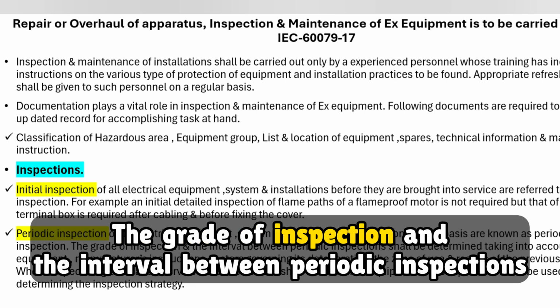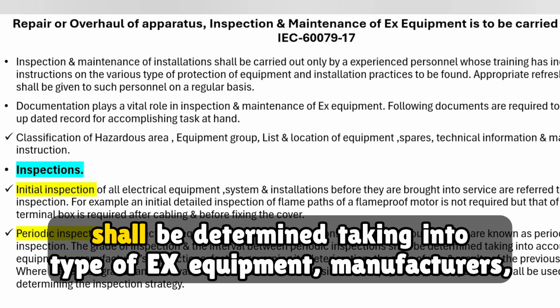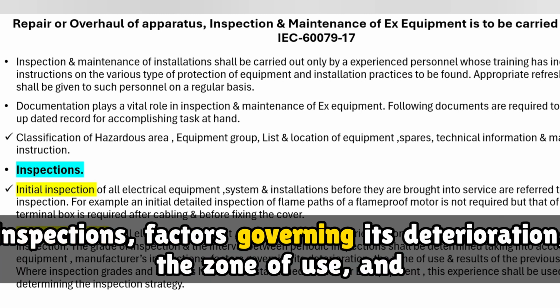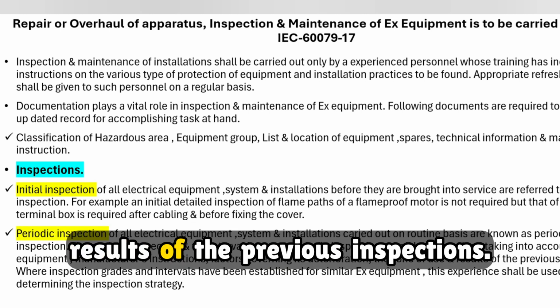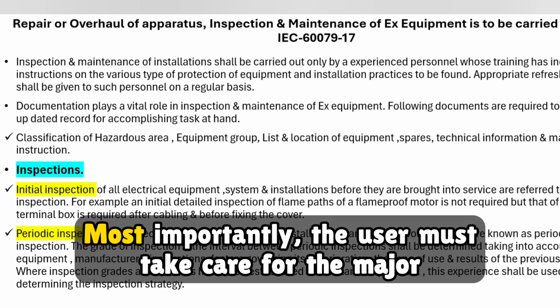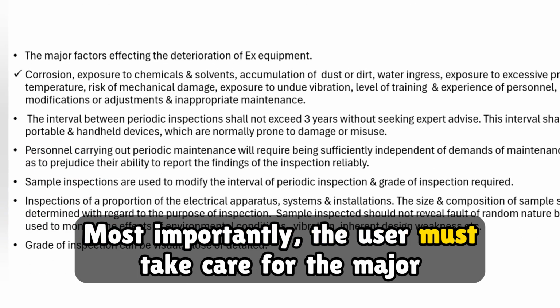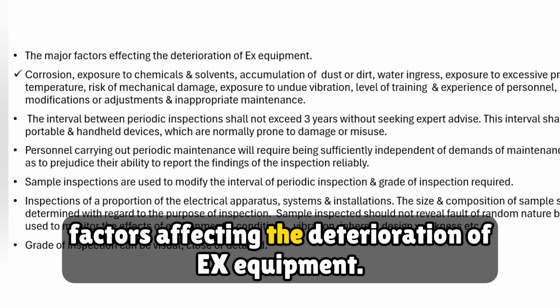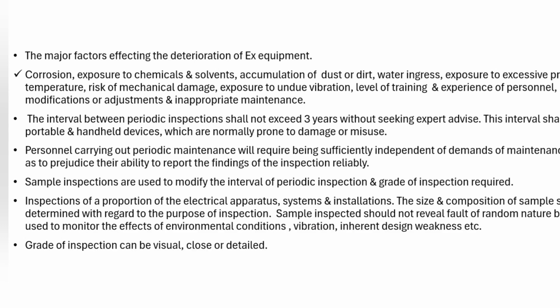The grade of inspection and the interval between periodic inspections shall be determined taking into account the type of EX equipment, manufacturer's instructions, factors governing its deterioration, the zone of use, and results of the previous inspections. Most importantly, the user must take care for the major factors affecting the deterioration of EX equipment.